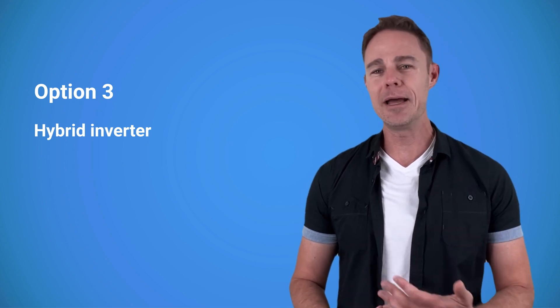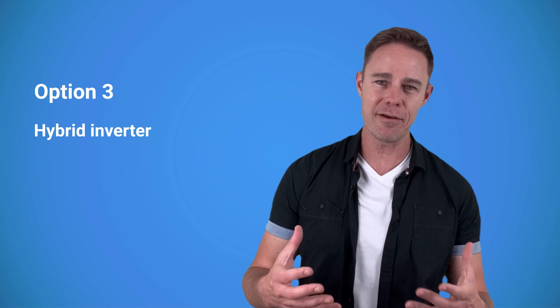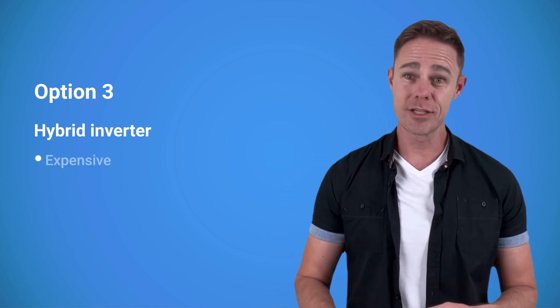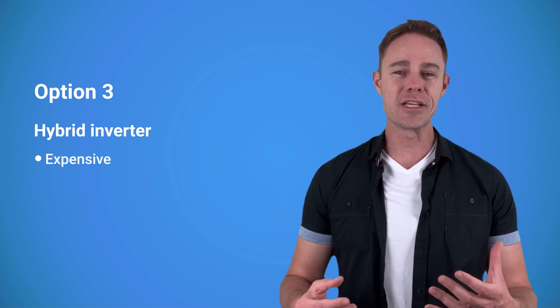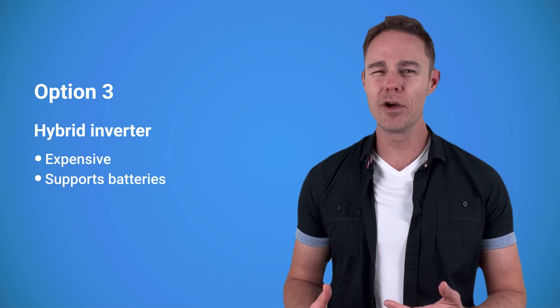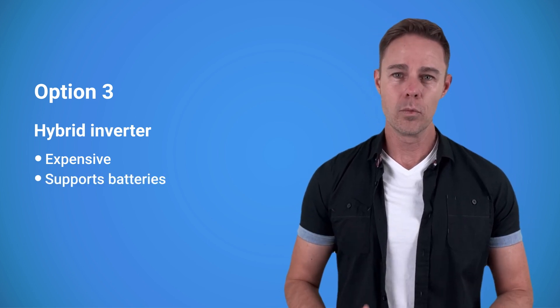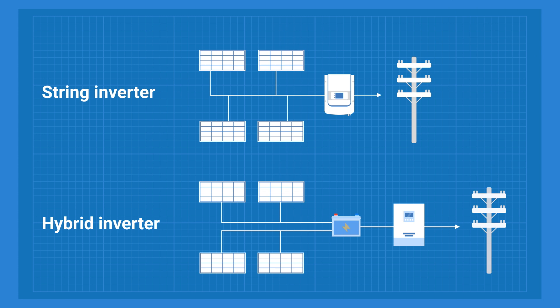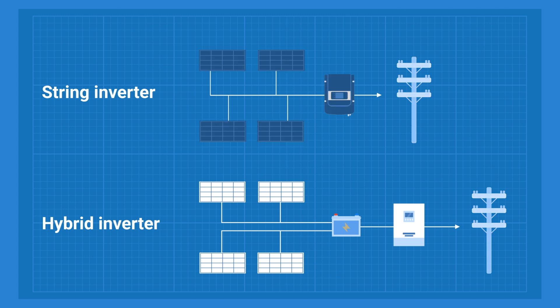What both the standard string inverter and micro inverters can't do is support a DC battery. You can add an AC battery such as the Tesla Powerwall to your system, but if the battery requires direct current, you're going to need a hybrid inverter. Hybrid inverters are the most sophisticated type of inverters and therefore cost the most. Such an inverter can act both as a grid-tie inverter and an off-grid one.